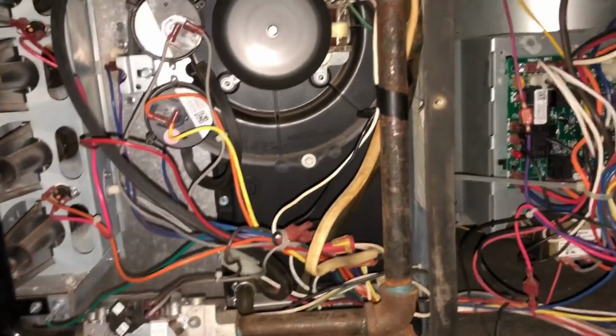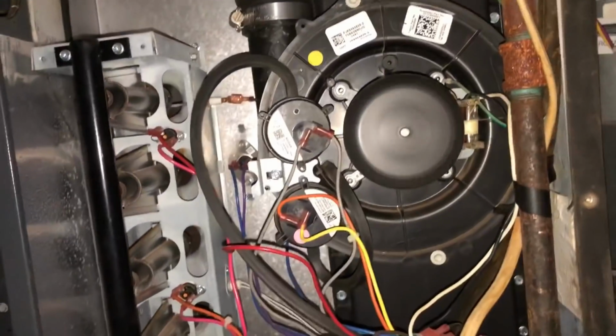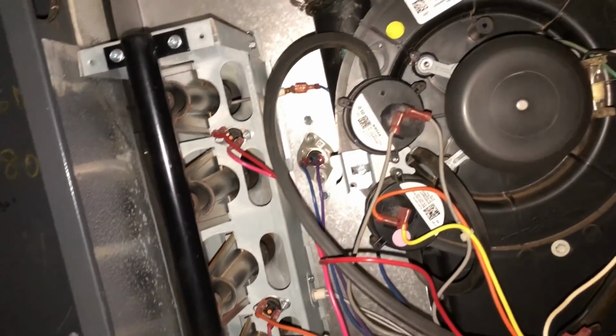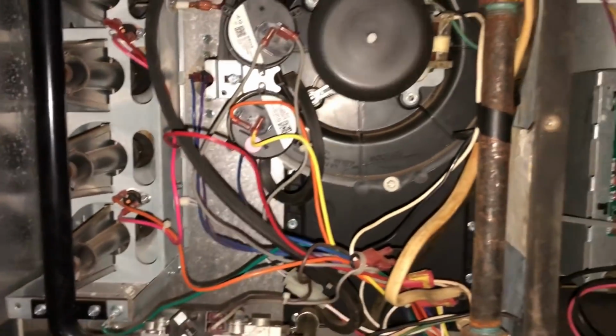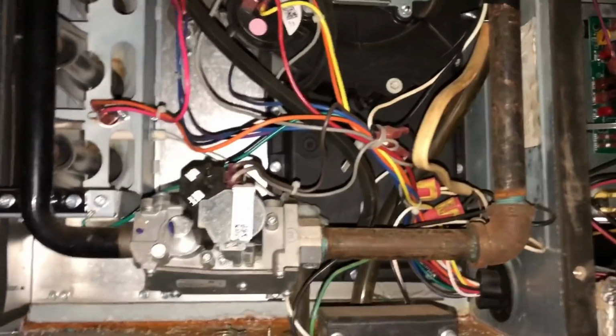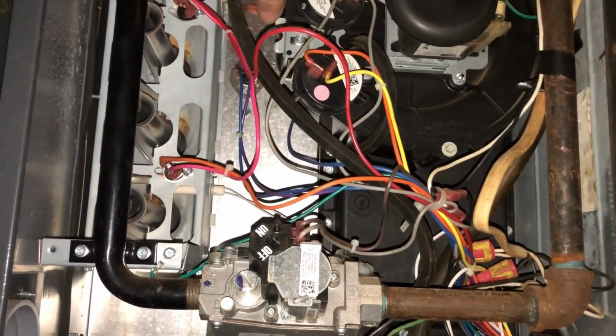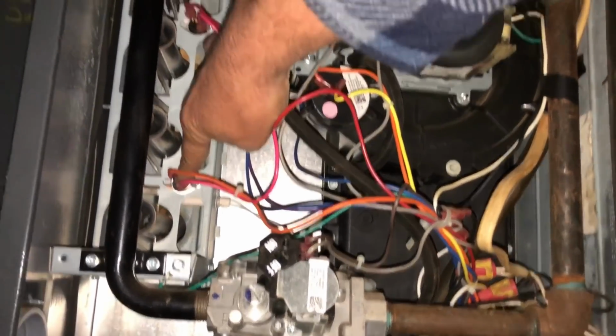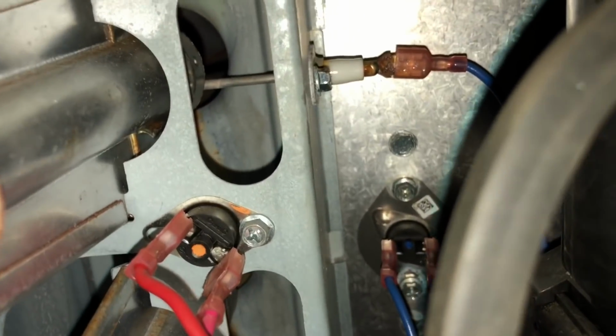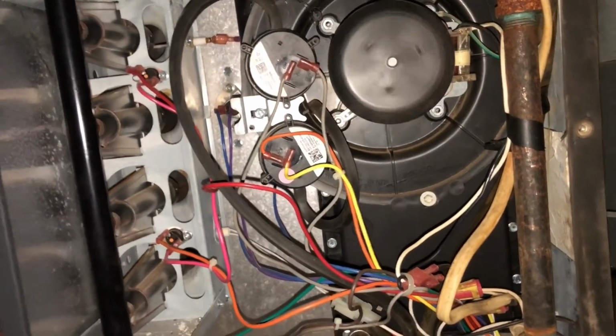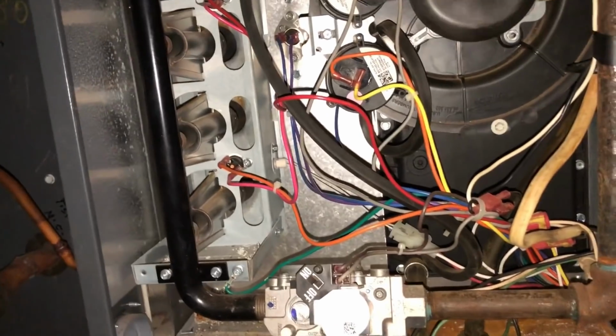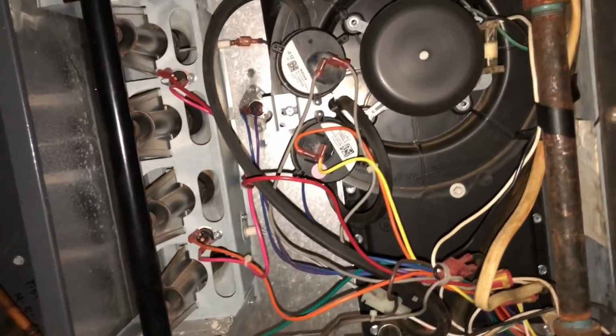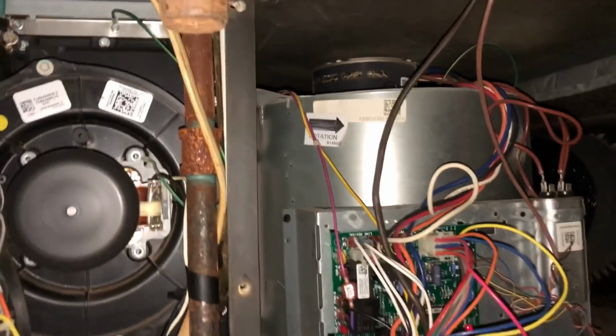Looked like six flashes. Probably something high limit related or rollout related to get continuous fan like that. Well, that rollout clicked as soon as I reached up there and touched it. Sure did. And now we're getting induced draft without the blower.